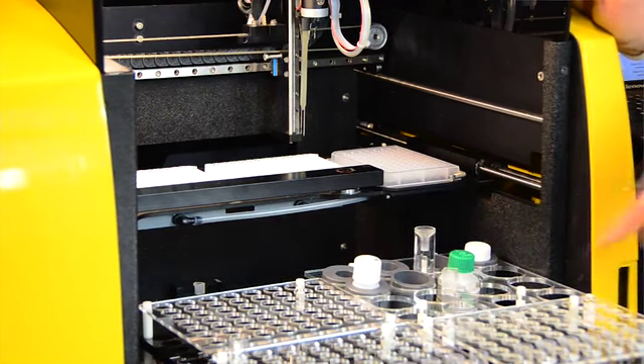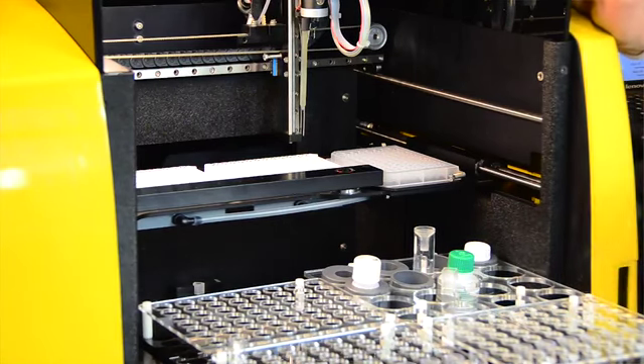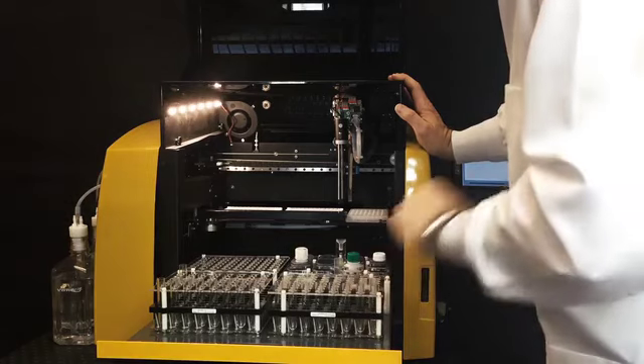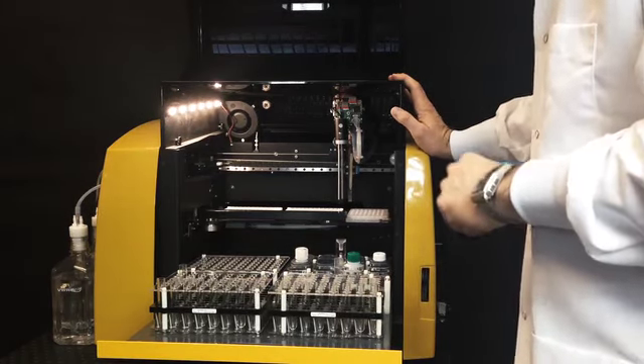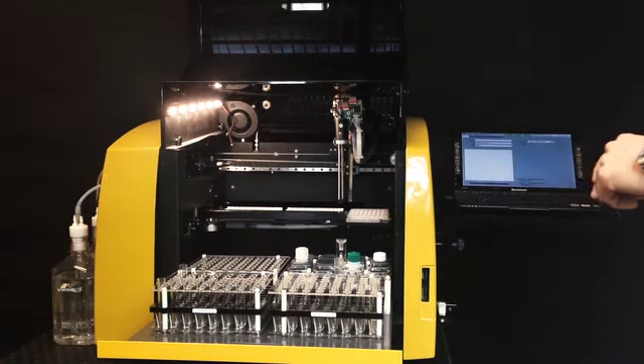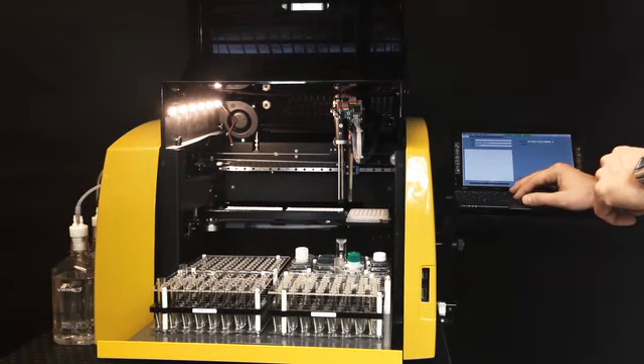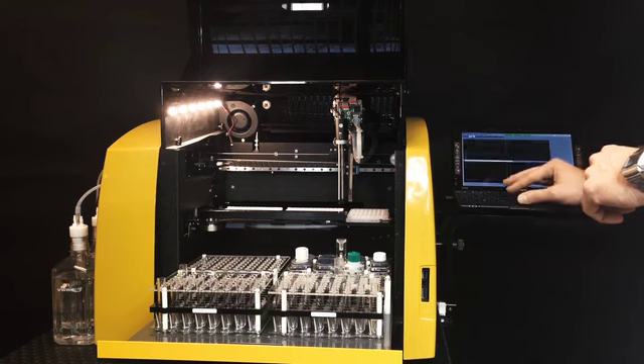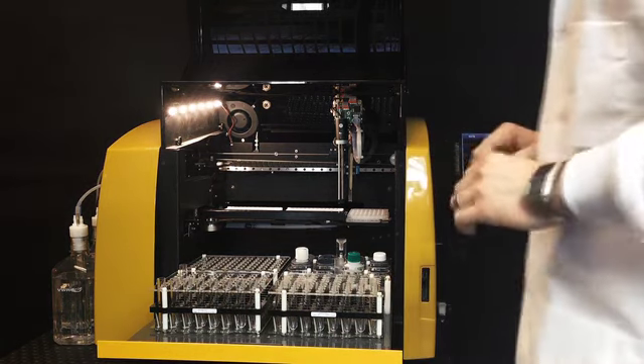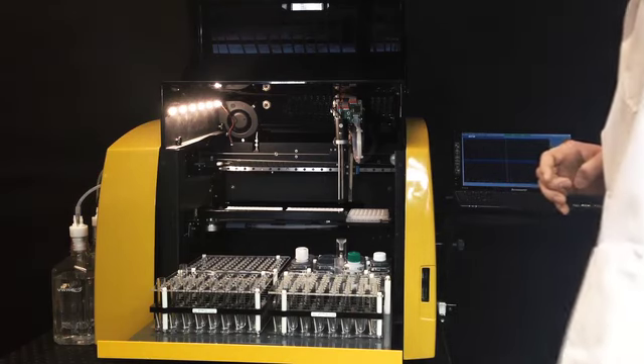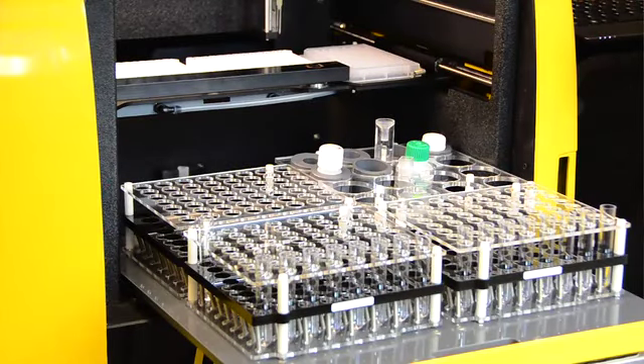The sample racks come in sizes of 12, 13, and 16 millimeters for all of the standard clinical lab testing samples. Those can also be custom made for your lab if you have odd-shaped tubes. Now, one of the important features of the intelligent rack is the positive sample identification. When scanning in samples, our system does not force you into using a rail system where everything must be placed in the correct order. In our system, you can custom load your samples how you like.